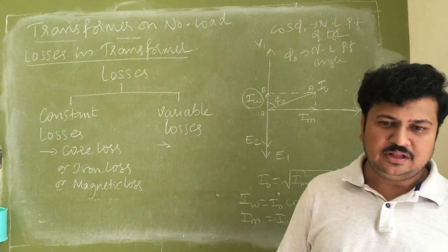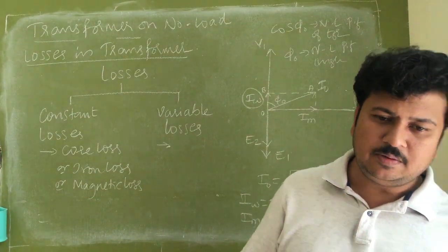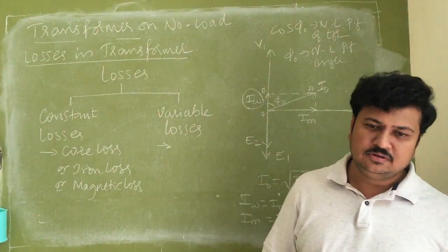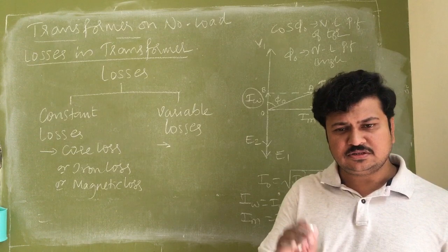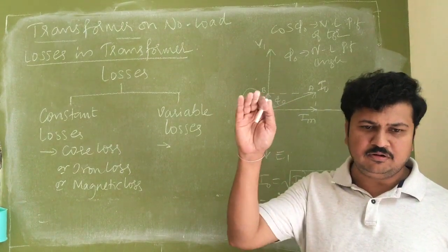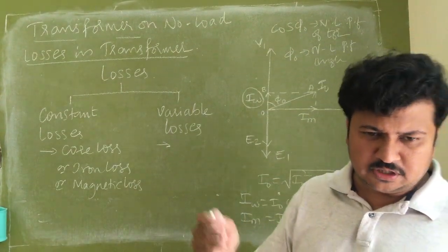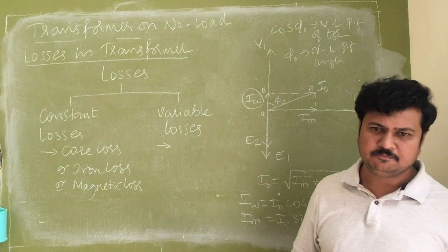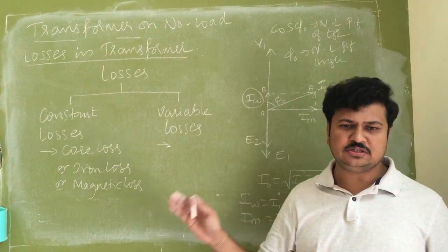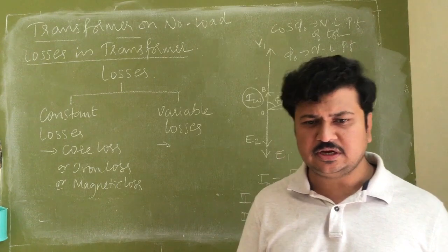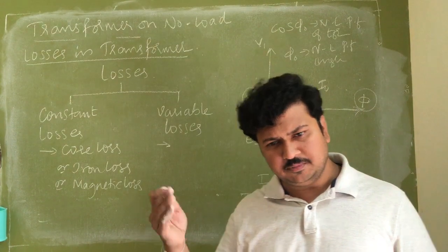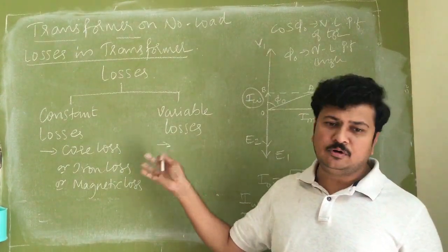So when I say this statement, many a time students will misunderstand that the magnitude of load is infinite. I am not talking about the magnitude of the load. I am talking about the variation of the load. Okay? The magnitude of the load is always equal to the maximum value of the load that a machine can withstand. Never is an electrical machine loaded beyond its withstanding capability or maximum load condition. Full load condition is one, maximum load condition is another. Generally, maximum load condition is taken around 10 to 15 to 20% above the full load condition.